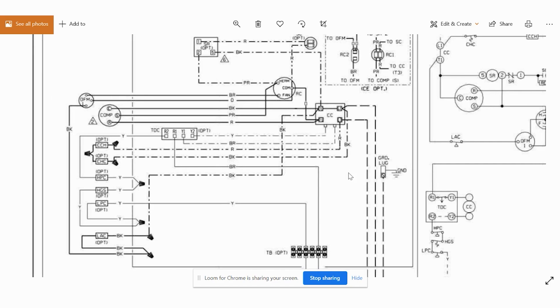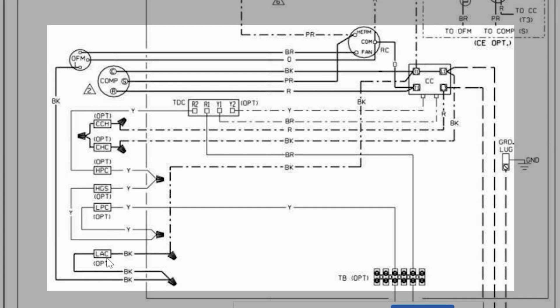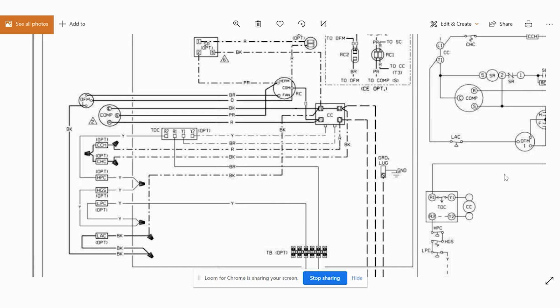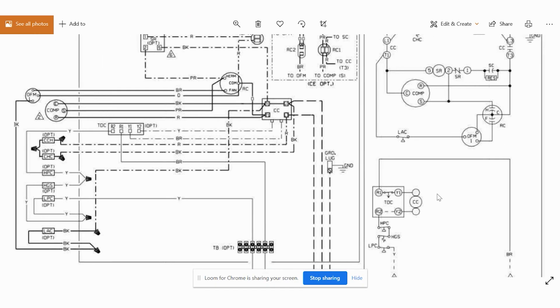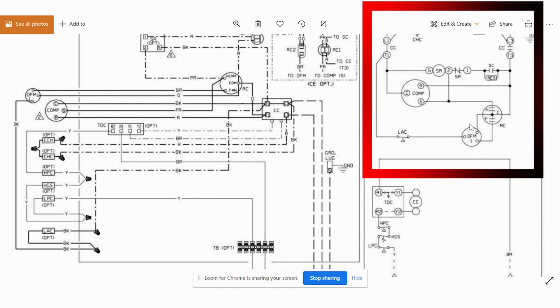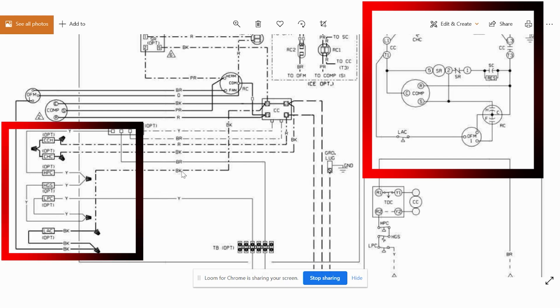If we look over on this side, let's see if we can find that. When this optional device is here, we actually wire through it. And so that breaks this circuit causing the condenser fan to go off when your pressure drops. So for those of you who are familiar with it, this is a type of a fan cycling control, but you can see over here that it's optional. And that's why we don't have it in the system that we're working on.